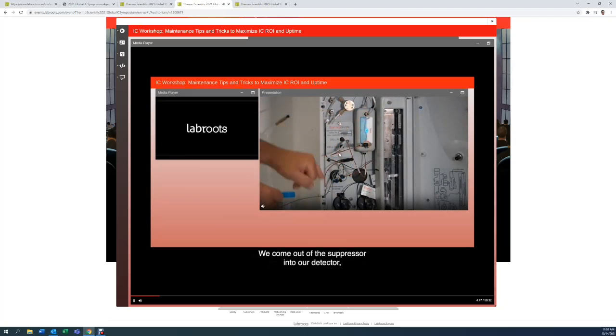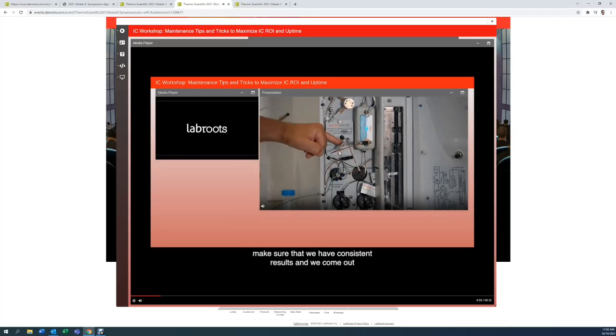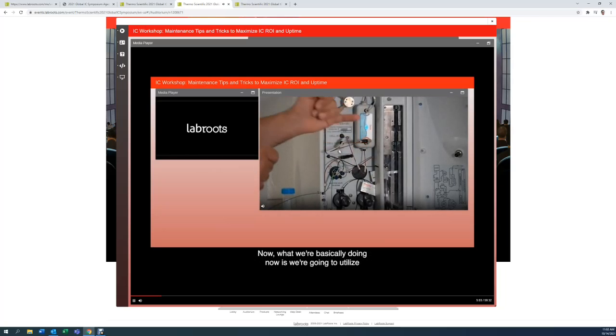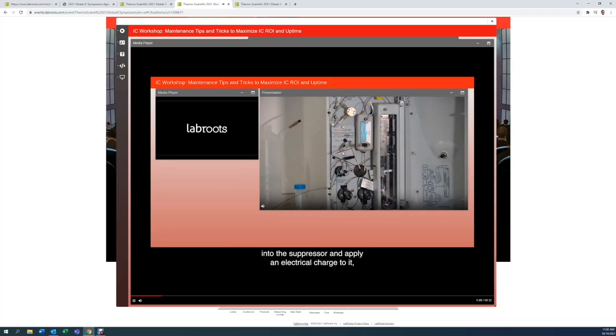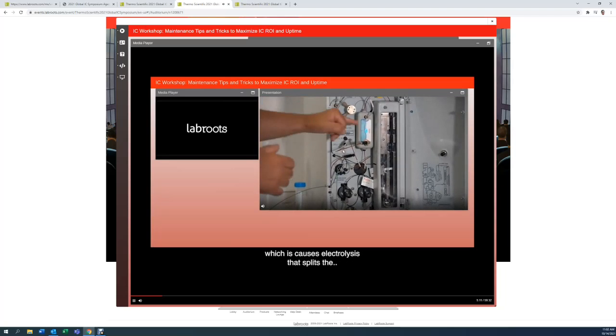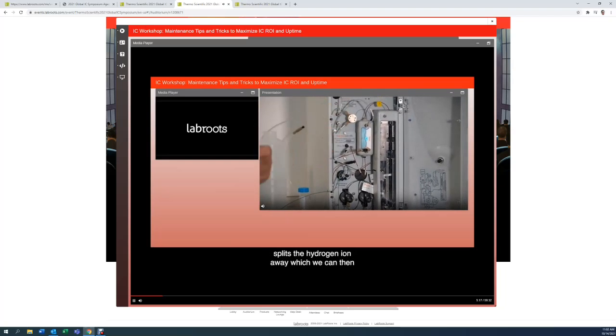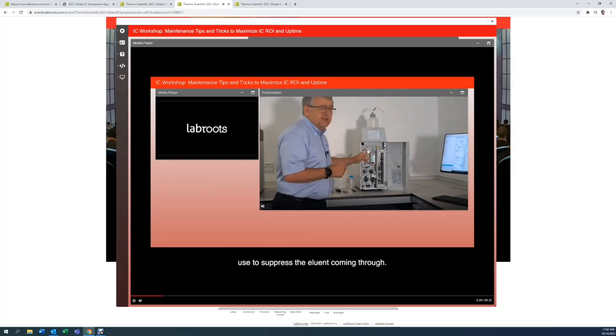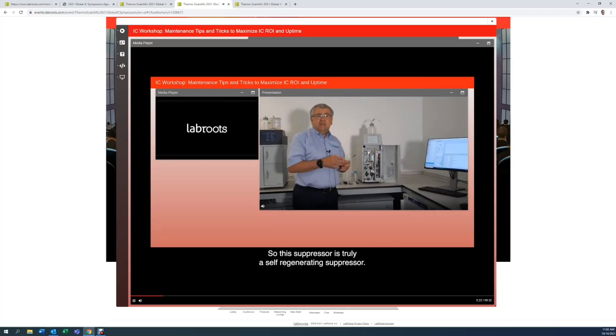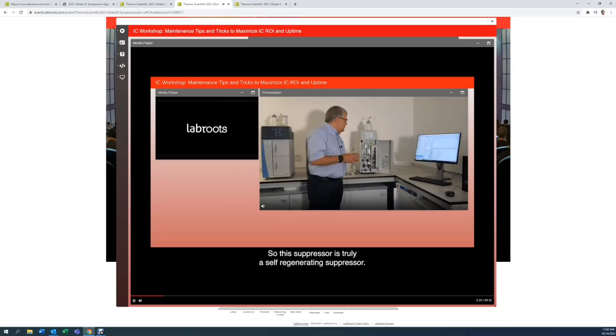We come out of the suppressor into our detector. It's a simple conductivity detector, which is again thermostated to make sure that we have consistent results. And we come out of our conductivity detector back into the suppressor. What we're basically doing now is utilizing that suppressed eluent, putting it back into the suppressor and applying an electrical charge to it, which causes electrolysis. That splits the hydrogen ion away, which we can then use to suppress the eluent coming through. So this suppressor is truly a self-regenerating suppressor.